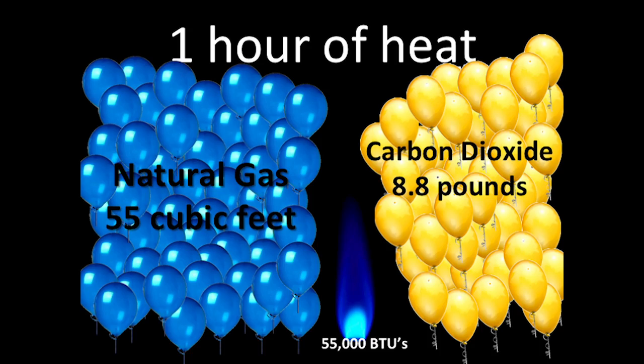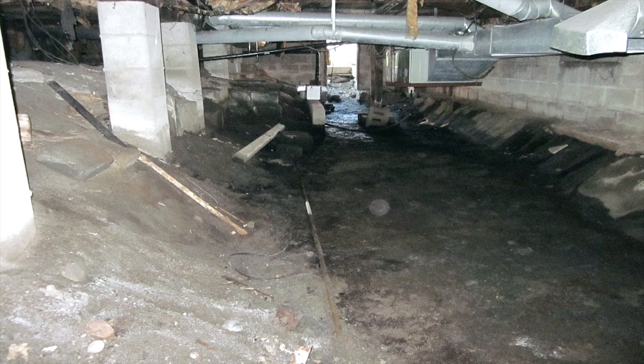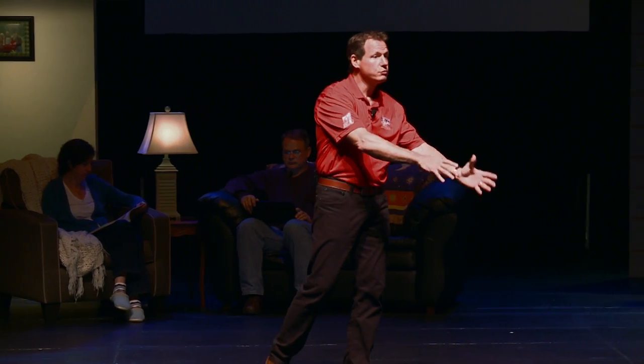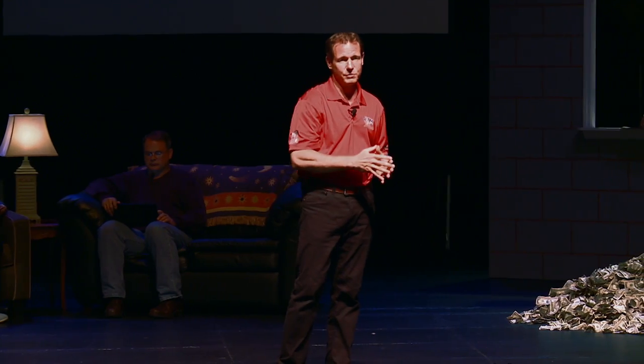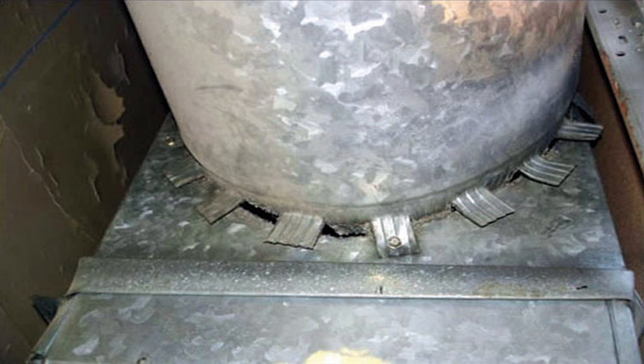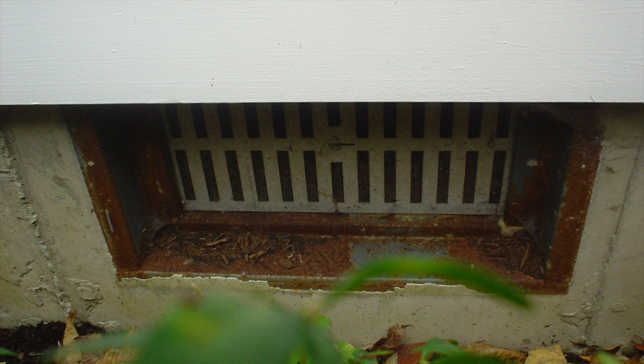By burning this gas or oil we release its BTU content. The furnace burns fuel to make hot air and sends it through a duct system to our rooms — and often this duct system is located in the crawl space. Cold winter air freely entering the crawl space vents cools those ducts. While the furnace makes 120-degree air, it may only be 95 degrees by the time it comes out of the heat registers. A furnace will have to run longer to heat a room with 95-degree air than with 120-degree air. Additionally, ducts have joints, and plenty of the air you pay to heat leaks out into the cold crawl space and is lost.